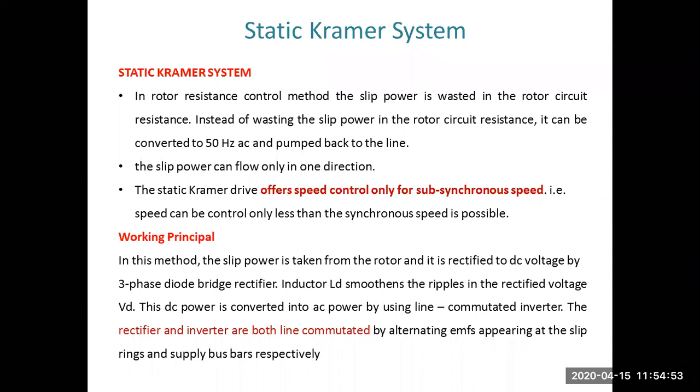The slip power can flow in one direction. This point has to be noted very carefully. The slip power can flow only in one direction. So the power will flow from the rotor to the feedback side, or from the rotor again to the supply system. Okay, the static Kramer drive offers speed control only for subsynchronous speed.